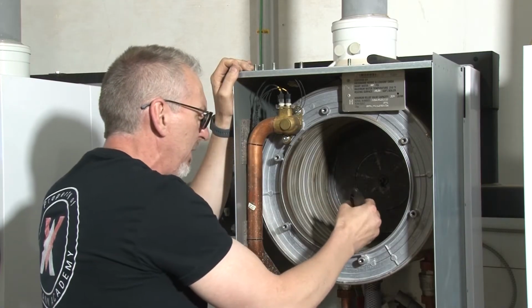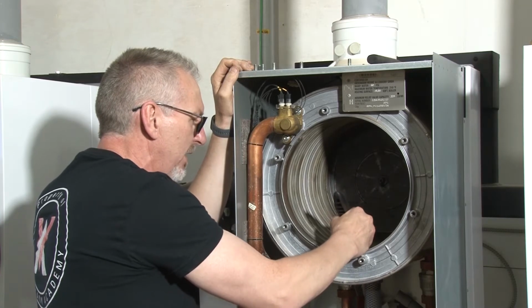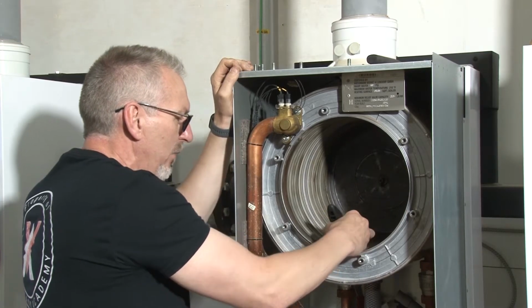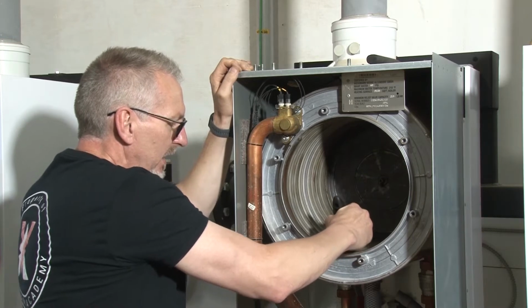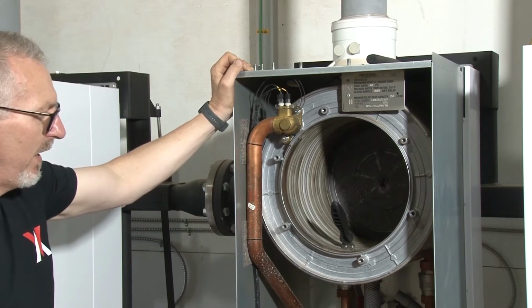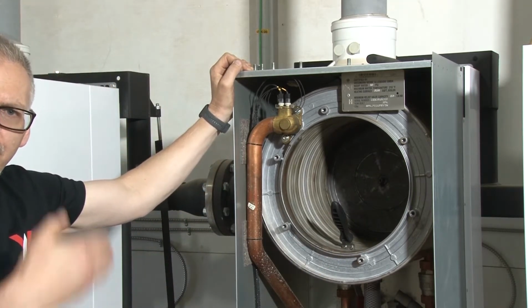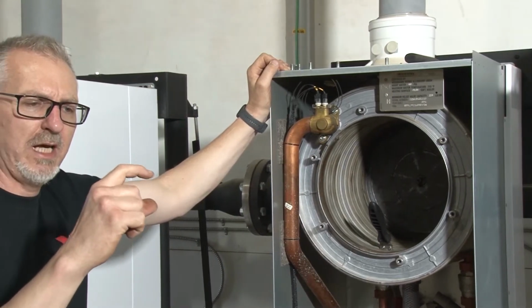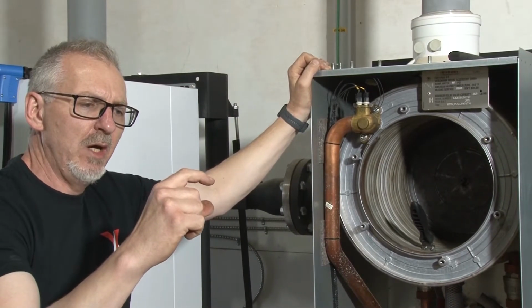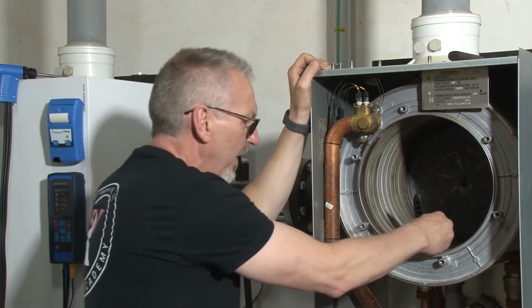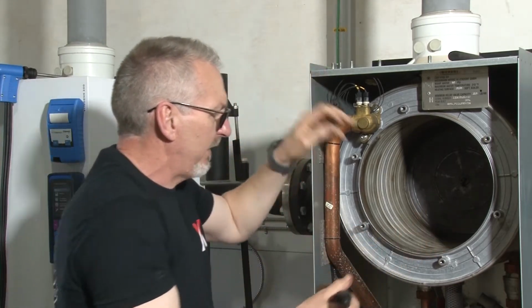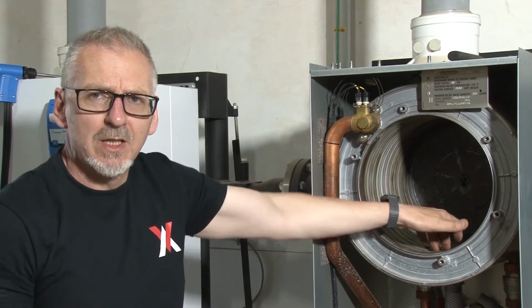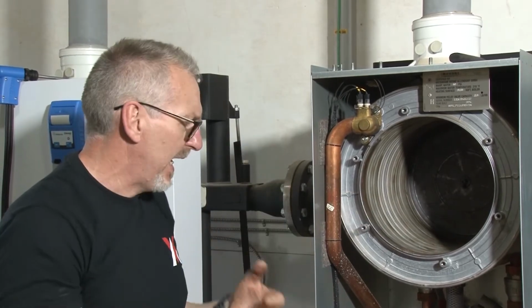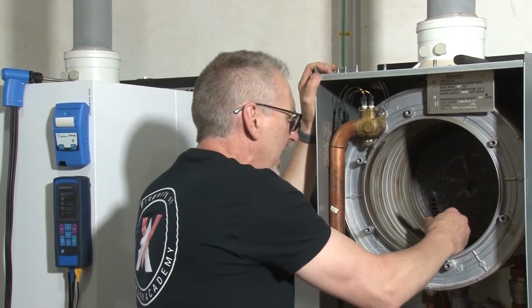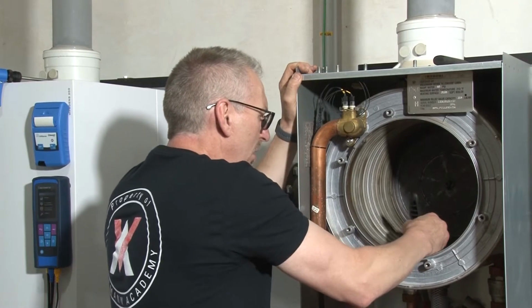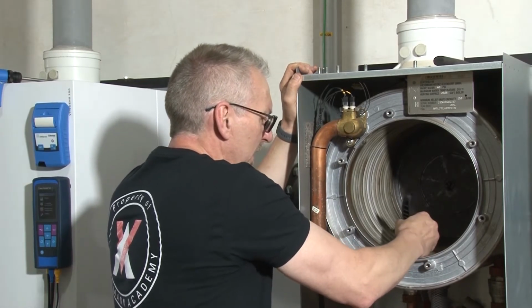The whole idea there is we want to make sure that we can get that tool in there so it bottoms out. That's pushed all the way through that water coil. That means that when we pull that cleaning knife out, that passageway there is now open. So when the boiler fires, all that flue gas can move through it nice and cleanly. And the idea is that we want to do all of these areas and clean them out.